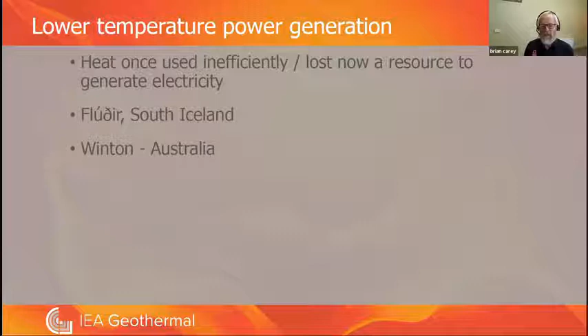In the Icelandic case, fluid leaves the wells at about 120 degrees Celsius and enters the district heating network at about 80 degrees Celsius. Before installing the power plant, the fluid was cooled by mixing with colder water to distribute 80 degree fluid to the district heating network. The power plant now utilizes the higher temperature fluid more effectively, using a 600 kilowatt, 4-module Kalina cycle system to drop the temperature from 120 down to 80 degrees Celsius before supplying the district heating network.